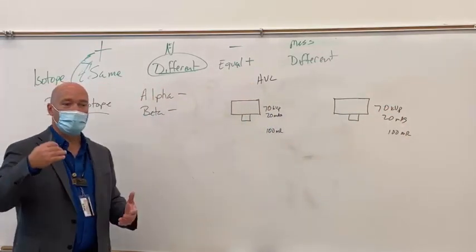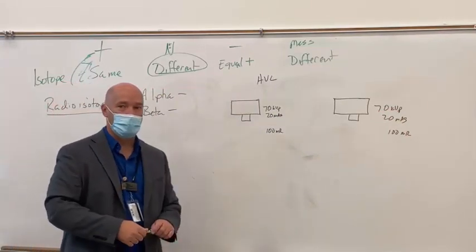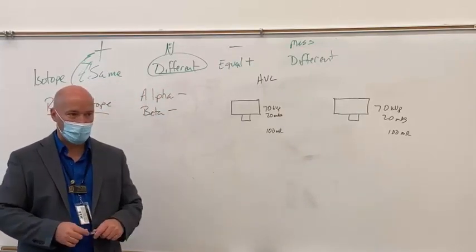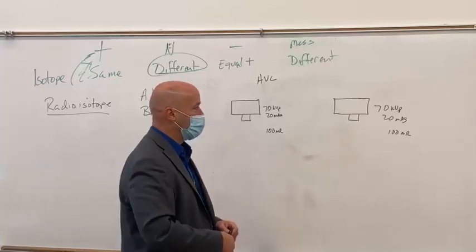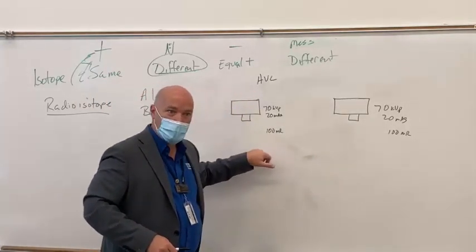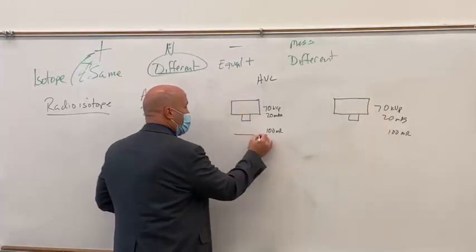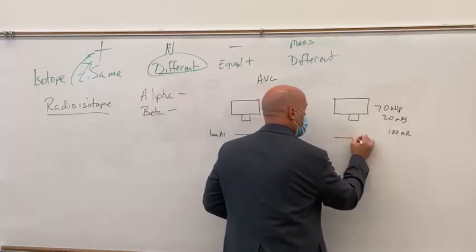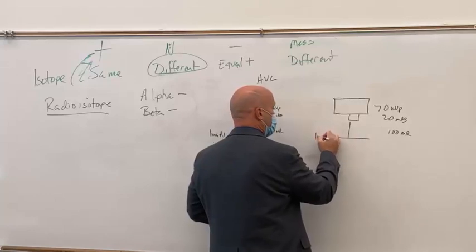one machine has greater levels of filtration, and what was the purpose for filtration? Filter out everything that's low energy. Low energy X-ray photons, right, so you filter out the low energy X-ray photons. But if you've got two rooms that are shooting with the same mR per mAs output, and you put 1 millimeter of aluminum in the X-ray beam, so the X-ray beam's gotta go through that 1 millimeter of aluminum.